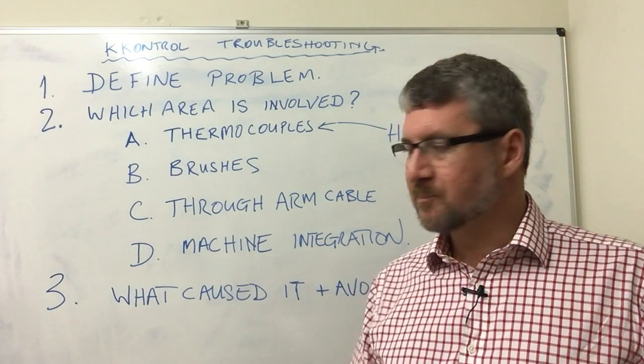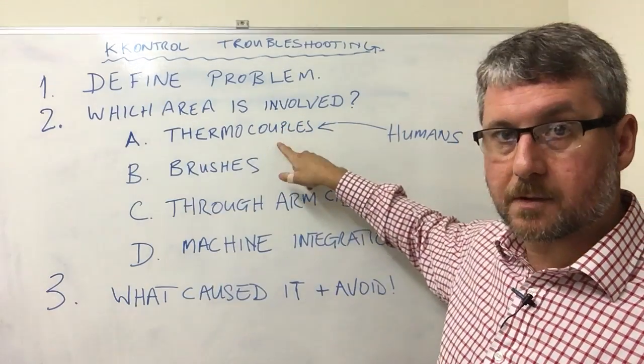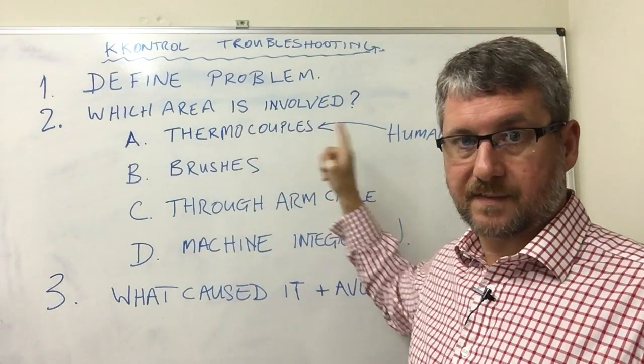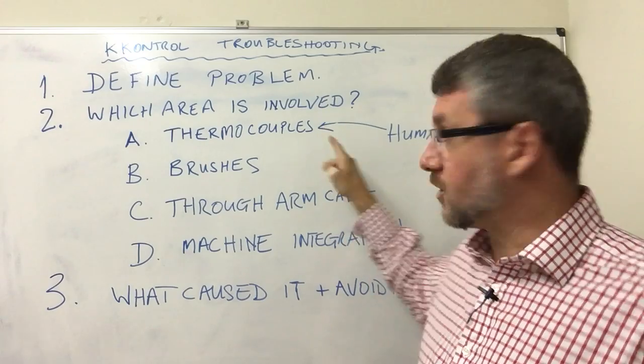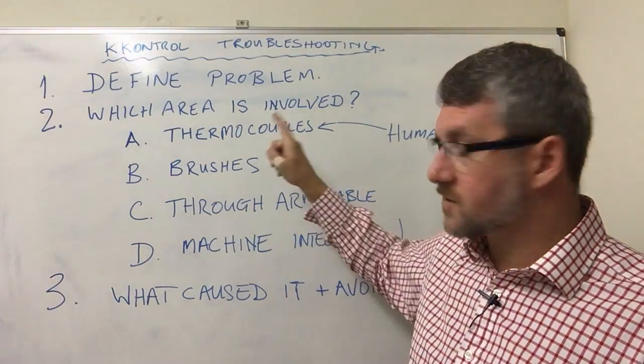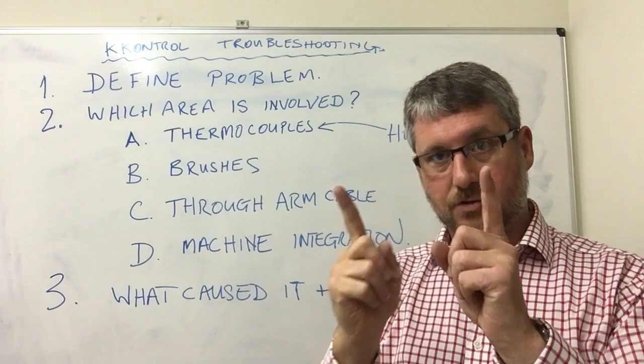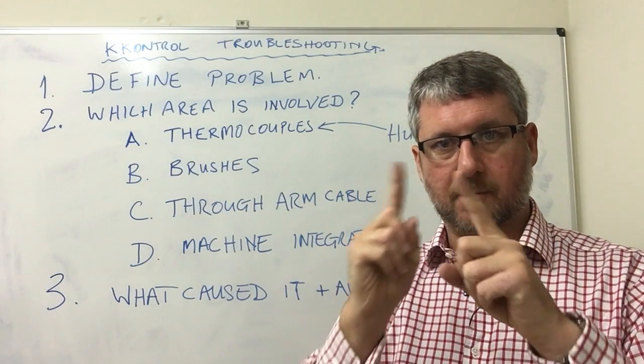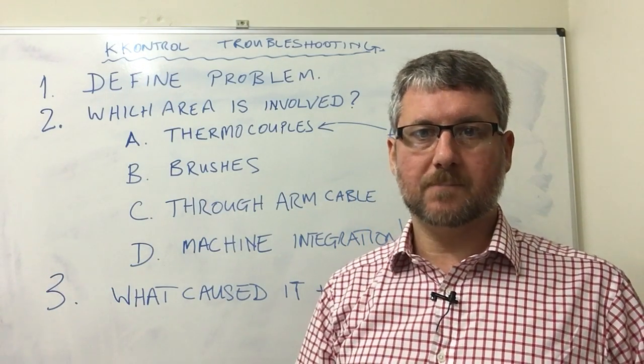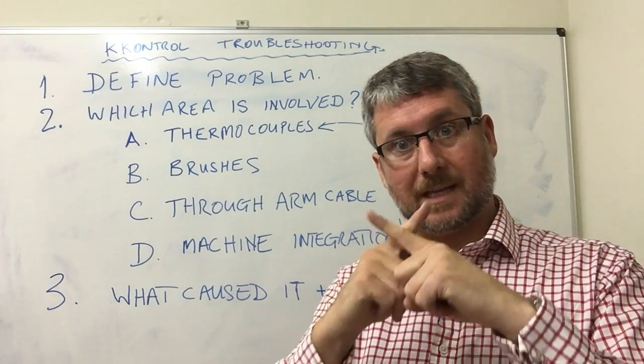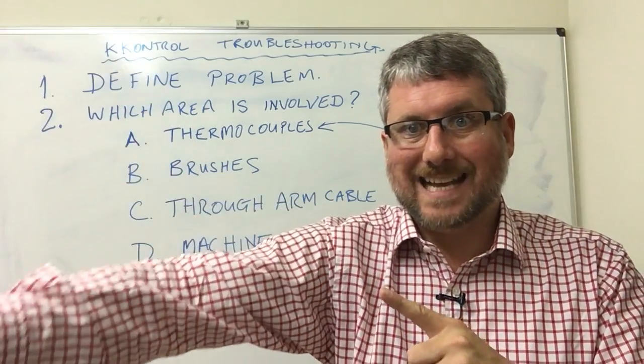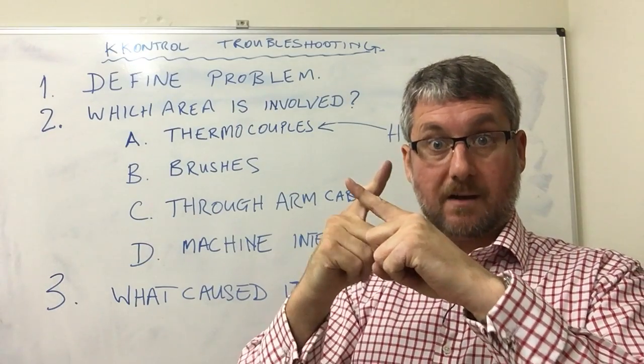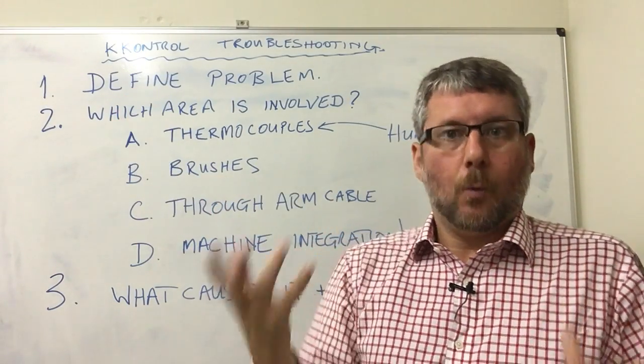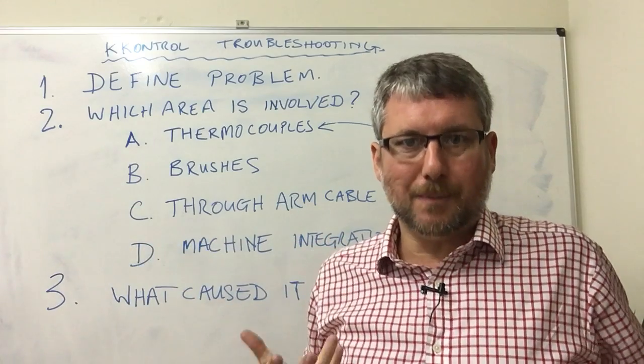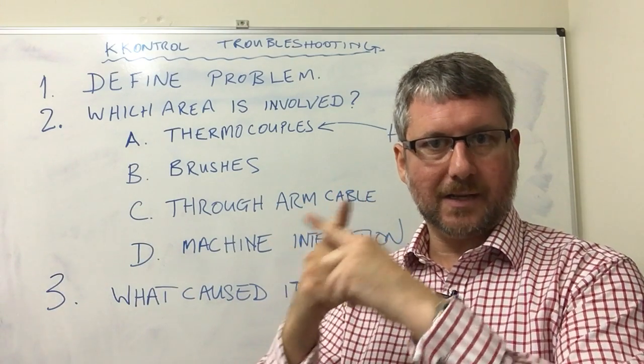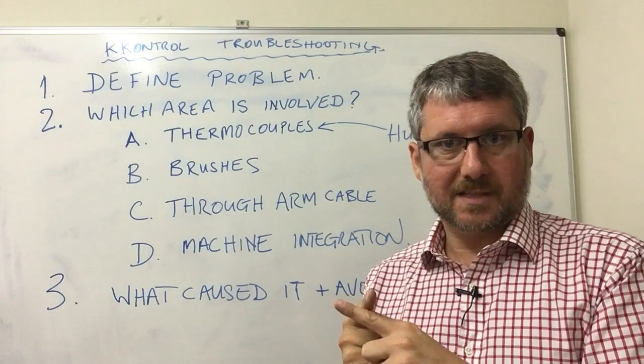And why is that? If there is a failure in the thermocouples, which is the top reason for failure in the system, if it's not caused by humans, it's usually because the two legs of the thermocouples have shorted out. And they're measuring the temperature at that point where they short out, not at the tip inside the mold, but where they have shorted out down the cable somewhere. Where is that cable going to be? It's going to be in the oven. So where they short out in the oven, they will measure oven temperature.